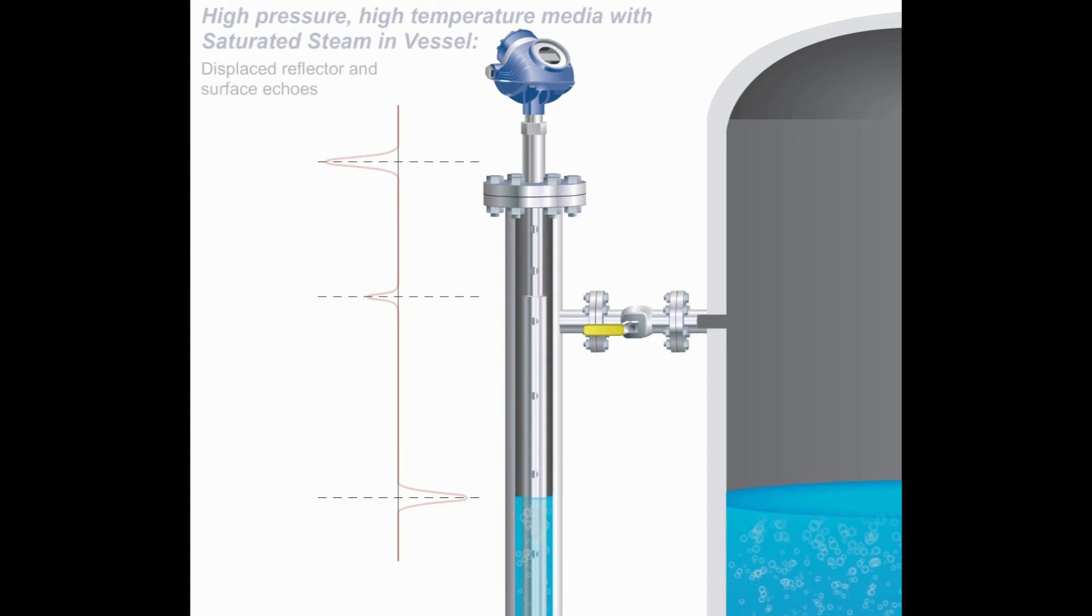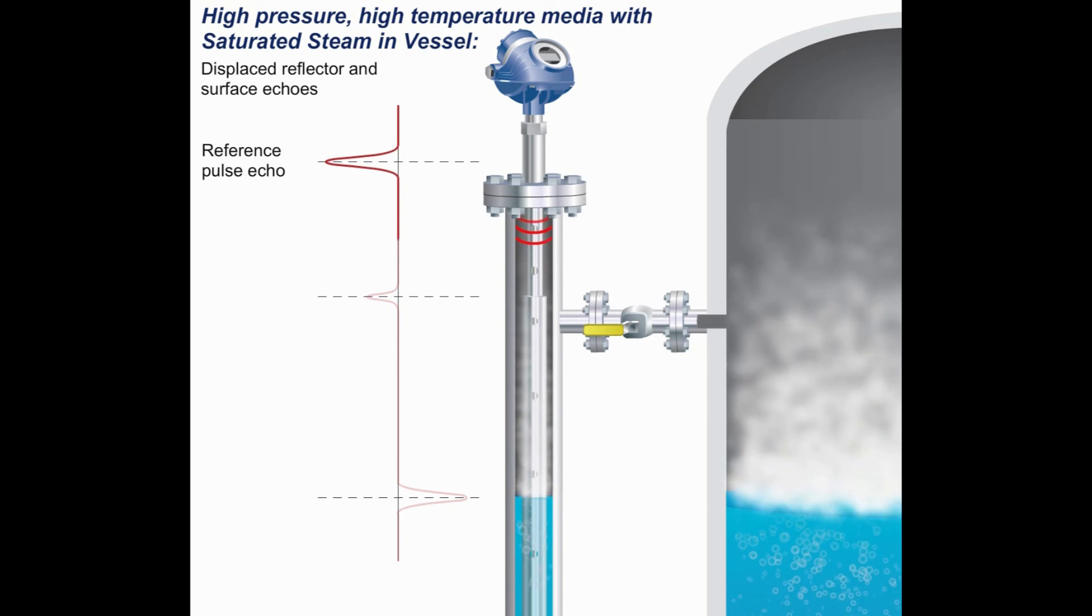A new case appears when high pressure saturated steam is added. Here you can see that both the reflector pulse and the surface pulse have been displaced due to the slower travel speed of the microwave pulses in the presence of steam.